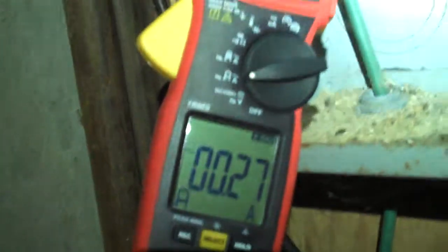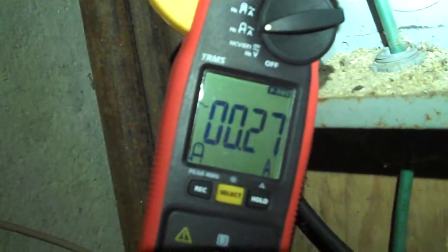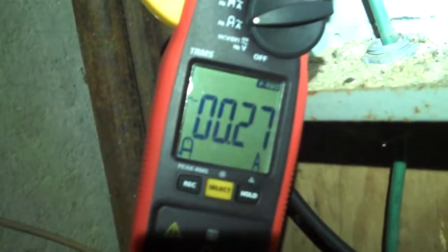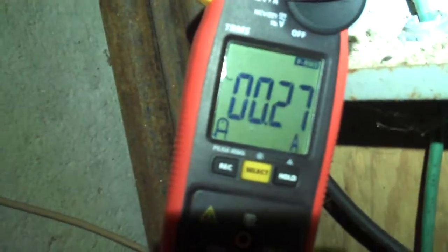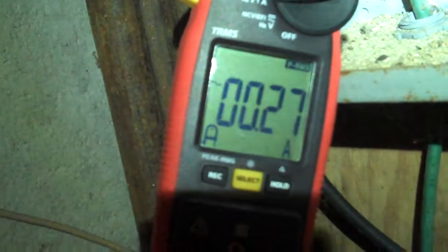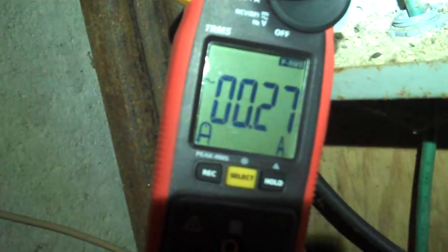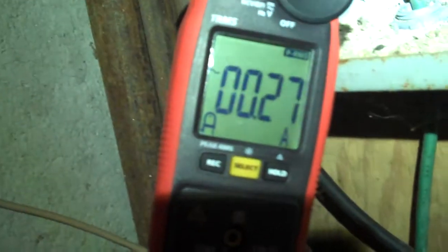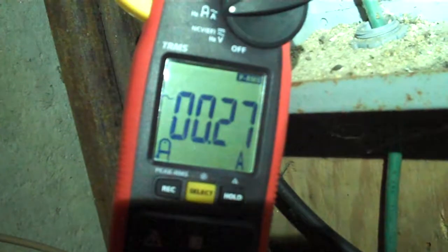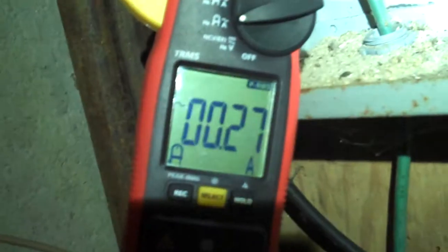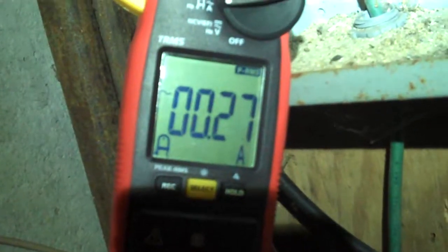The reason I'm doing this is because this pump or motor in the eone pump is spec'd at no more than 30 amps of inrush. Number one, I just want to verify what the actual inrush current is. The reason is that I want to be able to run this off of a generator, and generators are spec'd for the maximum current they can provide for starting a motor. They call it the surge current, but it's the same as the inrush current measurement.